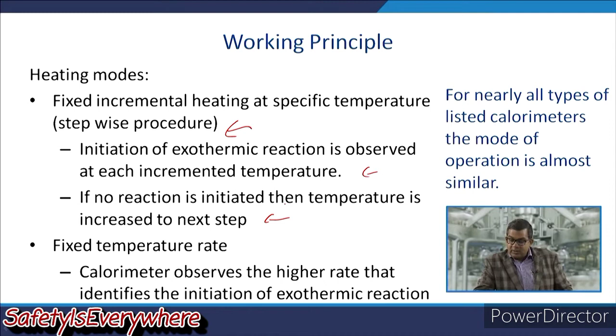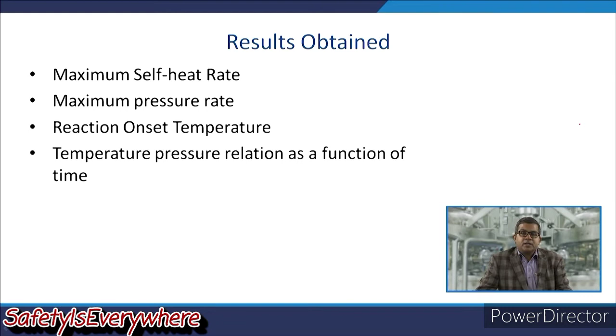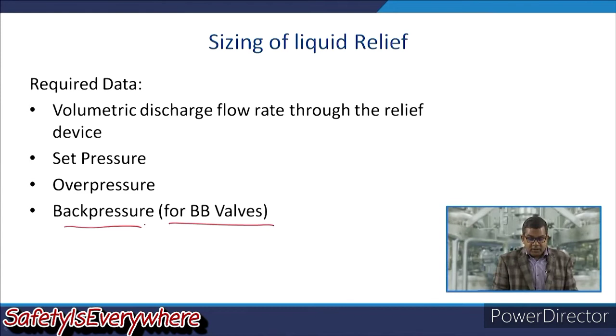Now, the results obtained under this: the maximum self heat rate, the maximum pressure rate, the reaction onset temperature, and the temperature and pressure relation, usually as a function of time. So, whenever we perform the sizing of liquid relief, we require various sets of data, like the volumetric discharge flow rate through the relief device, that depends on the opening of the relief device. What is the set pressure of that relief device? What is the due consideration of the overpressure in the process? And we need to consider the back pressure, especially for BB valves.